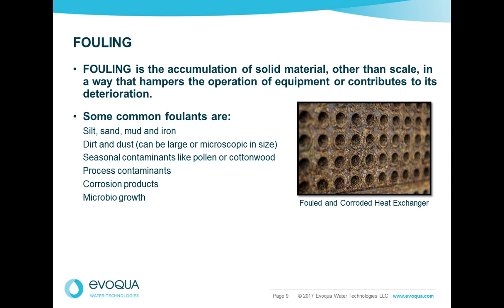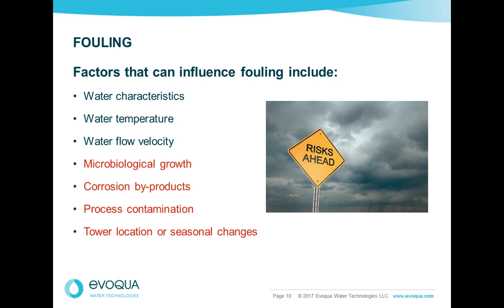Fouling is the accumulation of solid material, other than scale that hampers the way a cooling tower or heat exchanger operates and contributes to deterioration. Some common foulants are silt, sand, mud, dirt, dust, seasonal contaminants like pollen or cottonwood, process contaminants, corrosion products, and microbial growth. Factors influencing fouling include the water chemistry, the water temperature, and the water velocity. When you get low flow areas, dirt tends to settle out in those areas and can cause short circuiting. Other factors are microbiological growth, corrosion products, process contamination, and the tower's location. If it's in the middle of a construction site, you're going to have problems.